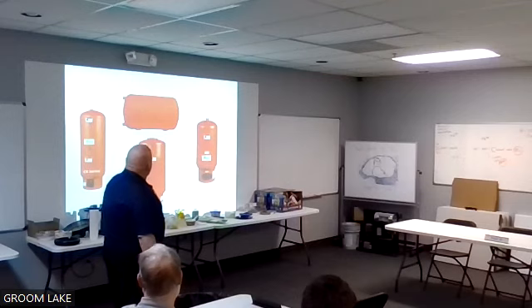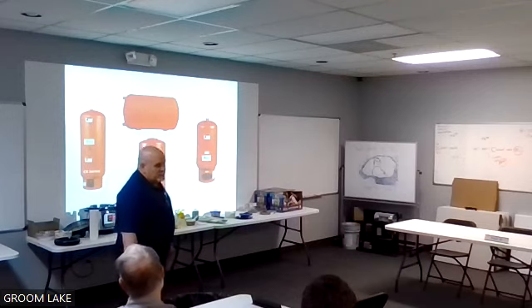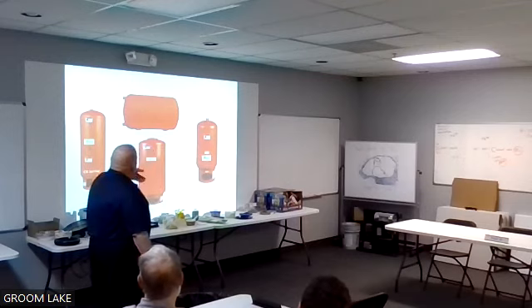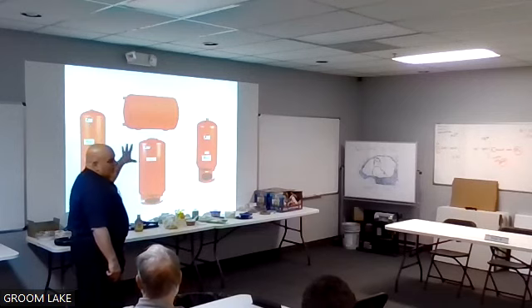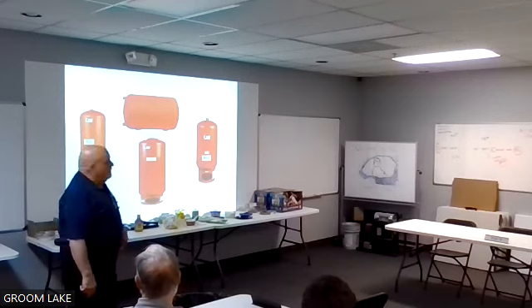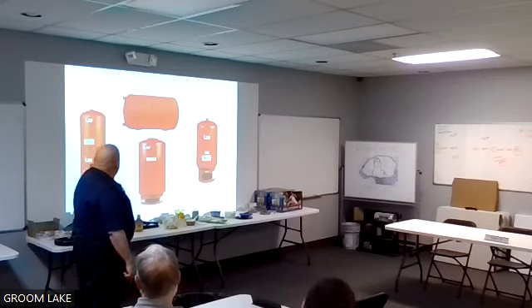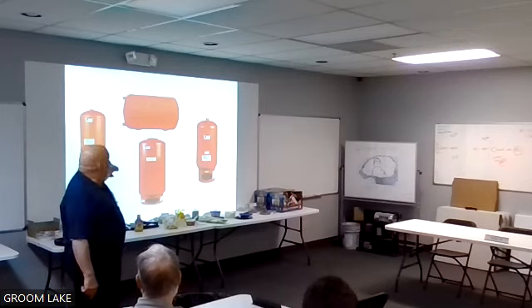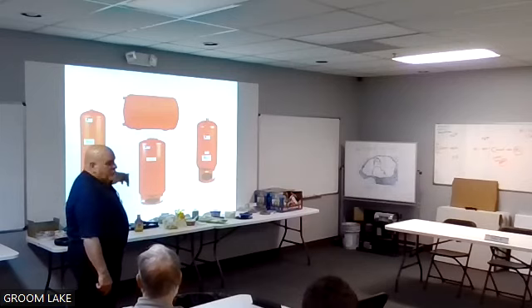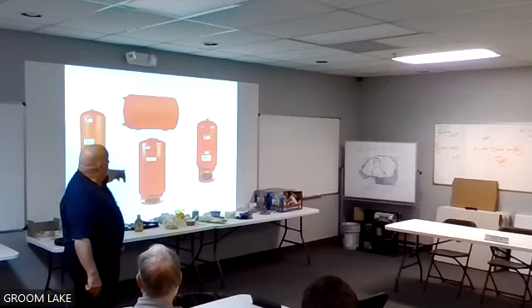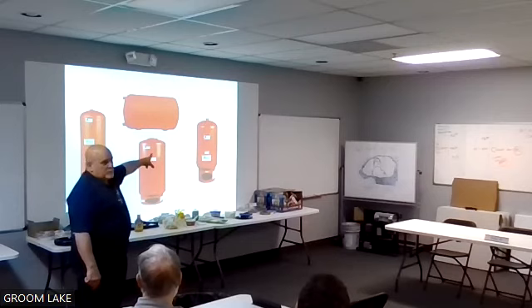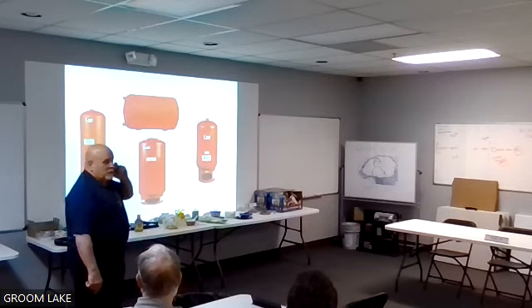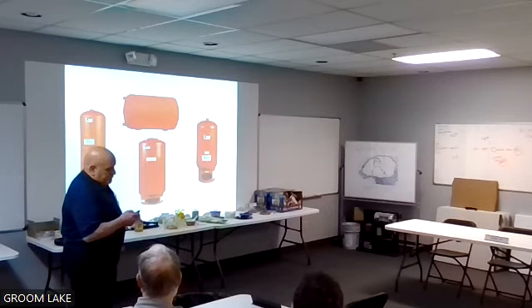These are the different kinds of expansion tanks. One of the Continentals is a plain steel tank. The drawbacks to those, and we're going to get into a little more depth, is that it's only filled by atmospheric pressure. These other 3 tanks: the CX series is a diaphragm tank. Then we have a full bladder tank, they call it. And we have a partial bladder expansion tank. We'll get into that a little more as we go on.